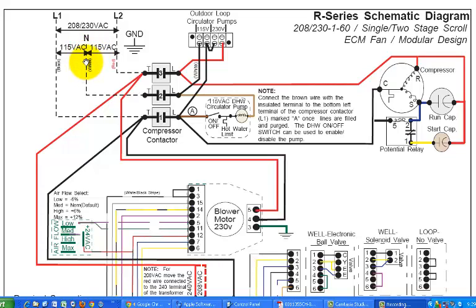So what this does with this 3-wire input, it gives us the option to pick off 230 or so volts for components that are going to run on that kind of voltage, and also allows us to pick off 115 volts for components that are going to operate on that lower voltage. So one of the key things about reading a schematic diagram is to be able to follow things through. And so we want to come up with the idea of being able to come along that L2, for example, and note that it's coming to this terminal point. The neutral line, it's coming over to this terminal point, and L1 again, of course, is coming over to this terminal point.